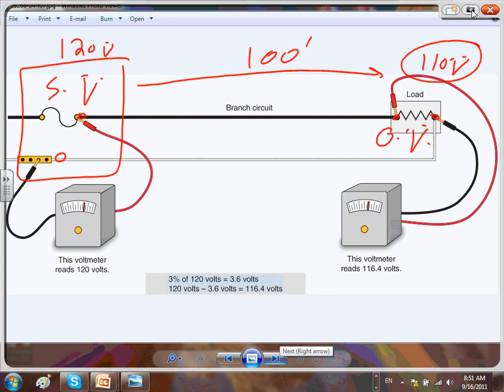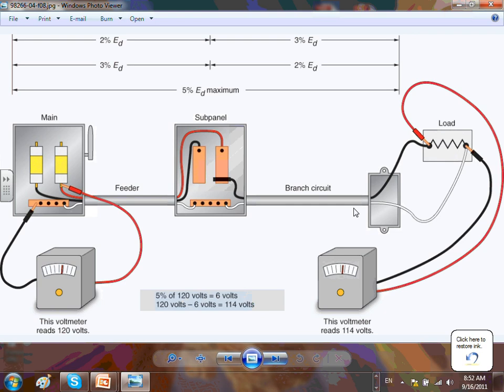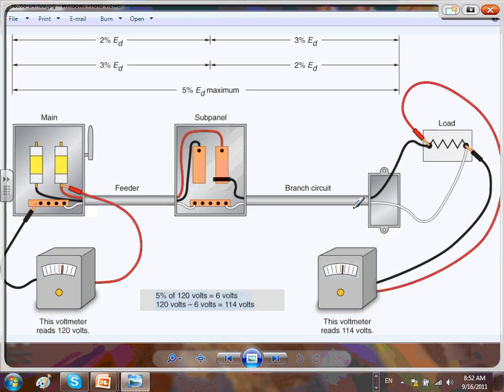The difference between the system voltage and the operating voltage is the voltage drop. Voltage drop is a recommendation in the NEC code book — Article 210.19a for branch circuits and Article 215.2a for feeders. If you go to these articles, it will tell you the voltage drop is recommended to stay within 5%.